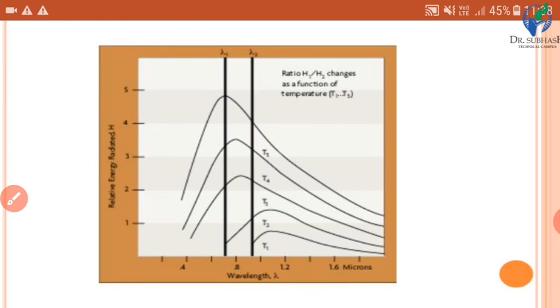Now what are the advantages? The ratio technique may eliminate or reduce errors in temperature measurement caused by changes in emissivity, surface finish, and energy absorbing materials such as water vapor between the thermometer and the target. So this is the solution or remedy for the radiation pyrometer. It means by using this technique we can reduce the error due to emissivity, surface finish, or some energy absorbing material like carbon dioxide, water vapor, etc.